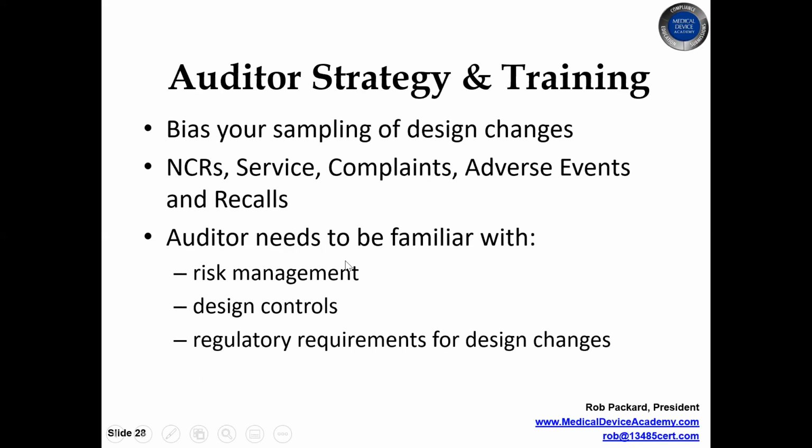And as I said, the auditor needs to be familiar with the risk management, the design control requirements, and all the regulatory requirements for design changes. So they should know those two FDA documents for device modifications, the Canadian significant change document and the European significant change document, and they should be familiar with the process of notifying their notified body, their importers, their distributors, and their authorized reps as economic operators for any changes to a CE marking product in the new MDR.